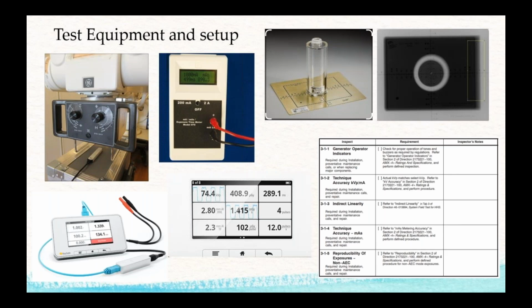If I'm shooting 100 kV, I want to make sure it's within 2 or 3% of 100 kV, depending on the manufacturer's specifications. I don't want it to be 110. I don't want it to be 70, because that anatomy and the program in the computer is set up for a certain kV and mAs, and that's what we want. So we have to ensure, as engineers, the accuracy of that.